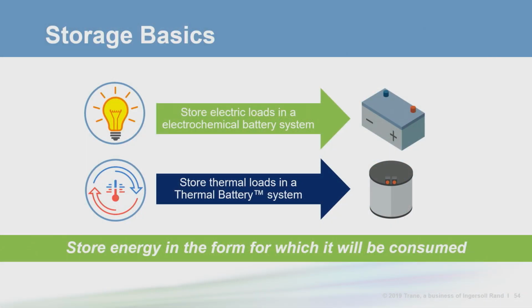When it comes to energy storage, you should always try to store the energy in the same form that it will be consumed, since that is the most efficient and cost-effective method. Store all of your electrical loads in an electrochemical battery system, and store all the thermal loads in a thermal battery system. Based on the economics, it does not make sense to satisfy the building thermal loads with an electrochemical battery.